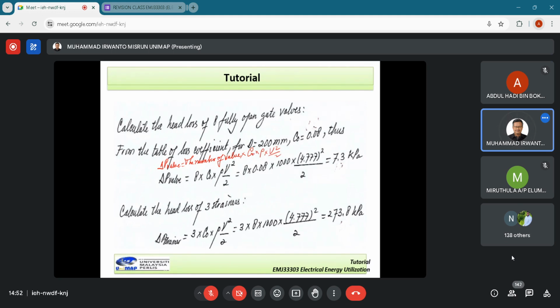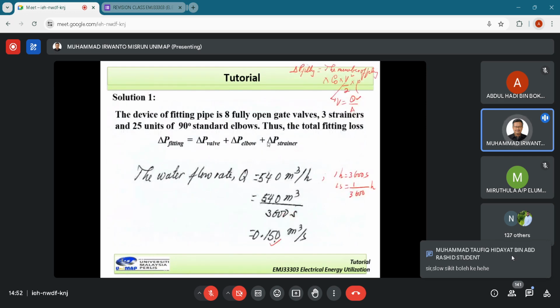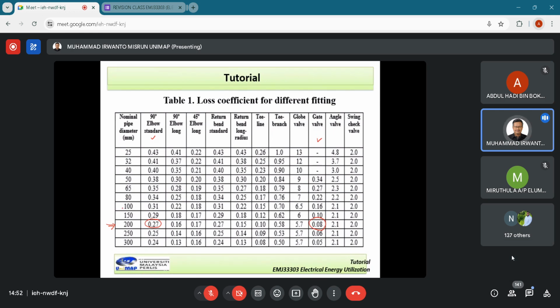Now for CO, since the type of valve is a fully open gate valve and the diameter of the pipe is 200 millimeters, referring to this table, we obtain CO is 0.08, based on the type of valve and the diameter of the pipe.